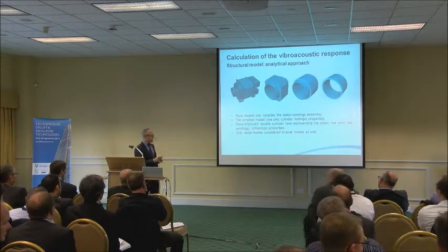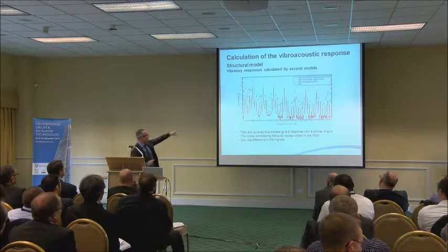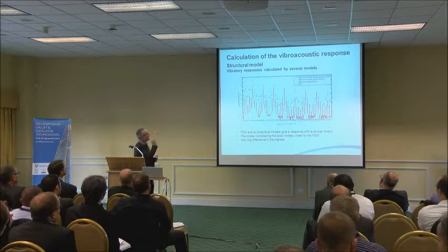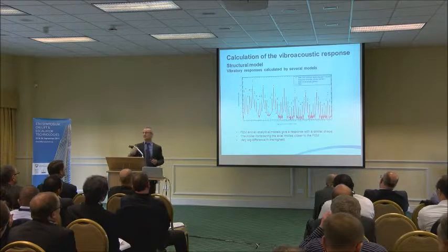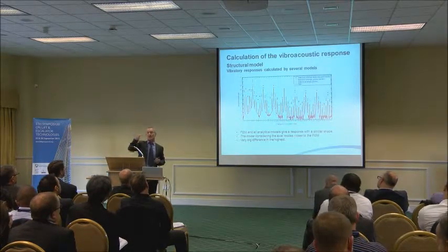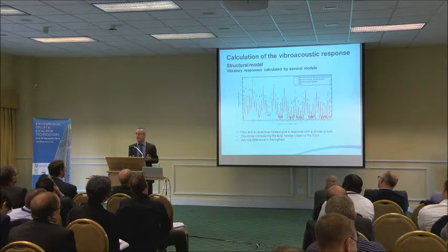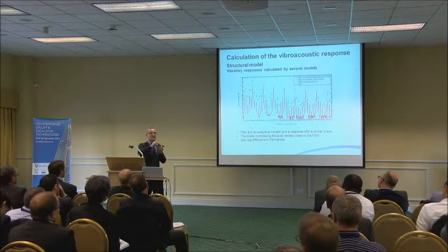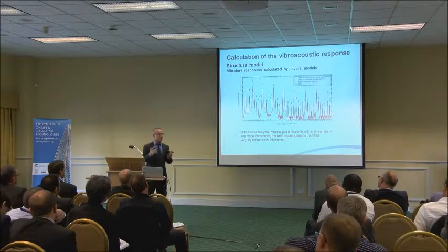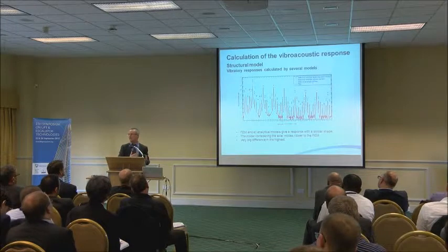We have done the calculations, and this is what we obtain. This is in red, the response given by the FEM model, and those points correspond to these analytical models I have commented. The magnitude for the analytical models is higher. Why? Because the model is stiffer. And it is stiffer because we have considered isotropic properties. And I said before that in the axial direction, the stiffness is much smaller than in the radial direction. So actually, the true machine is not so stiff as the analytical model.